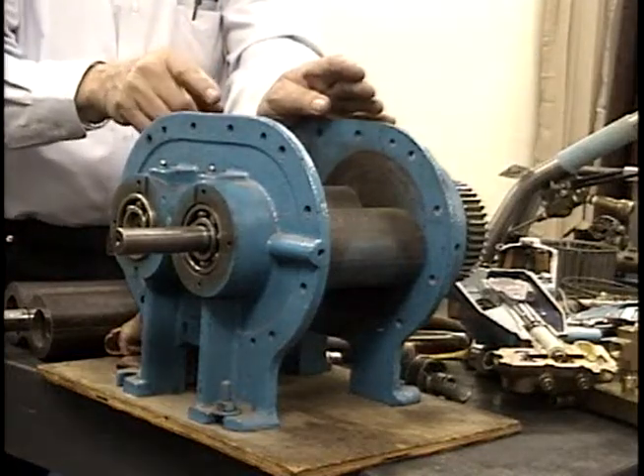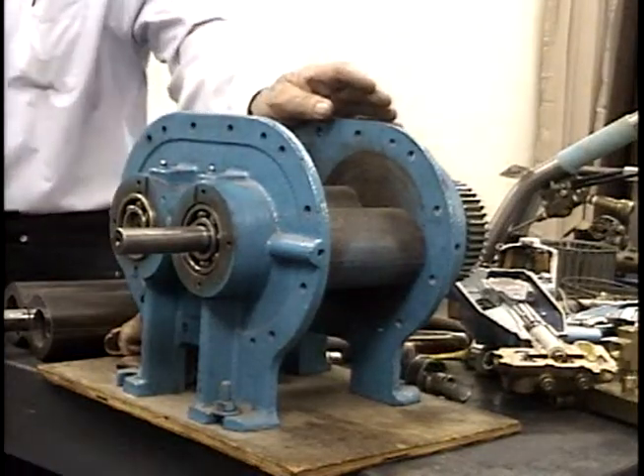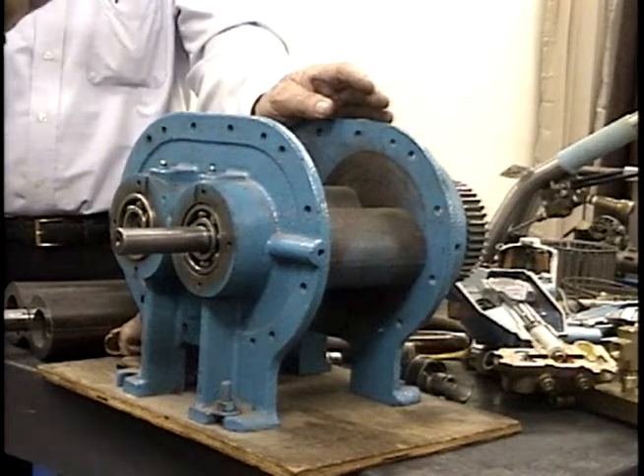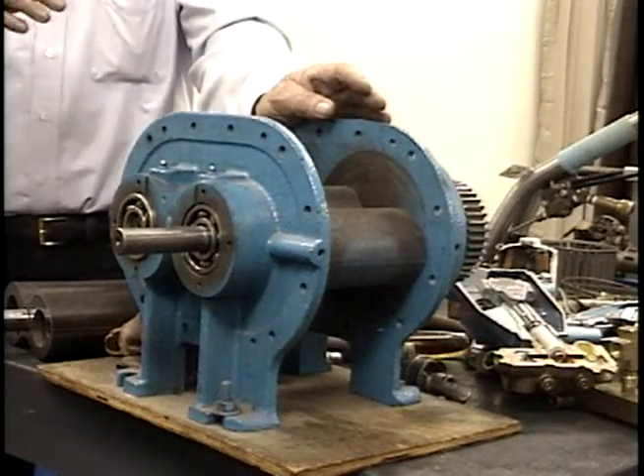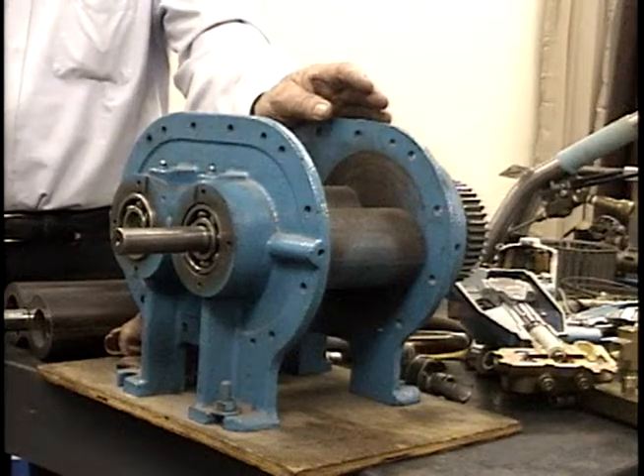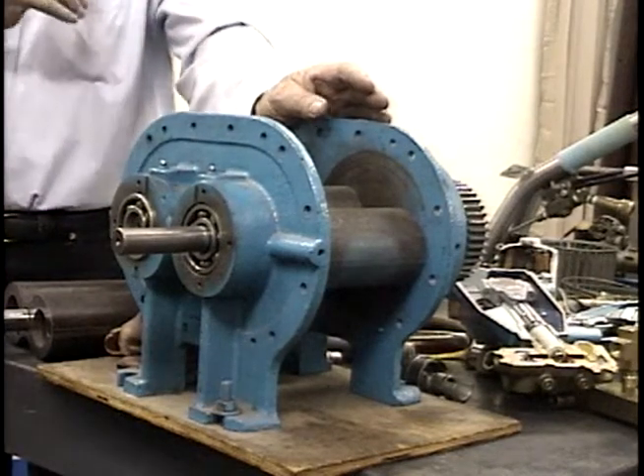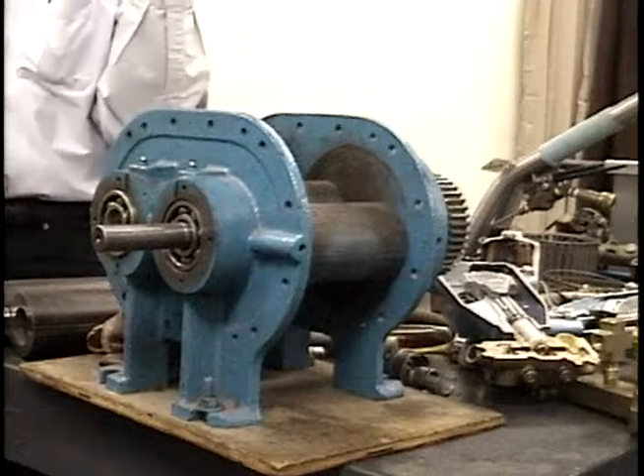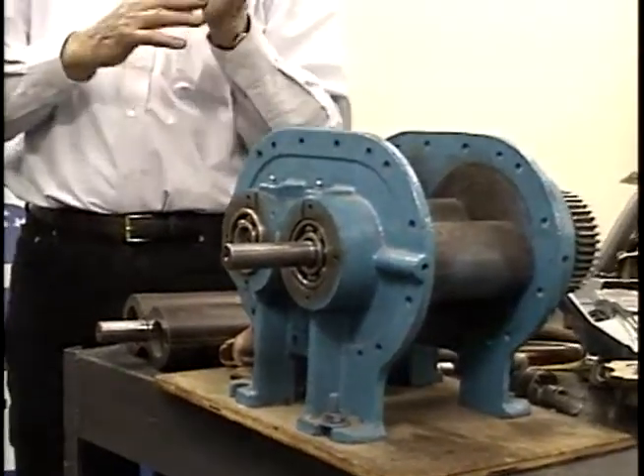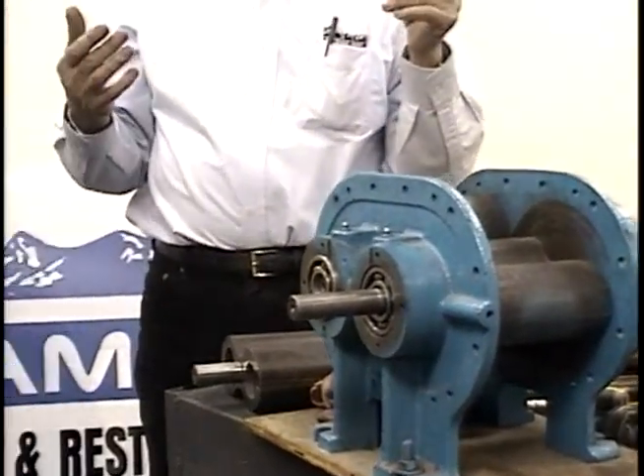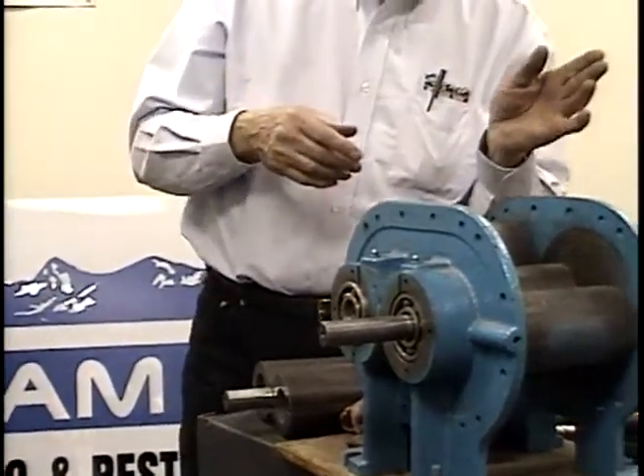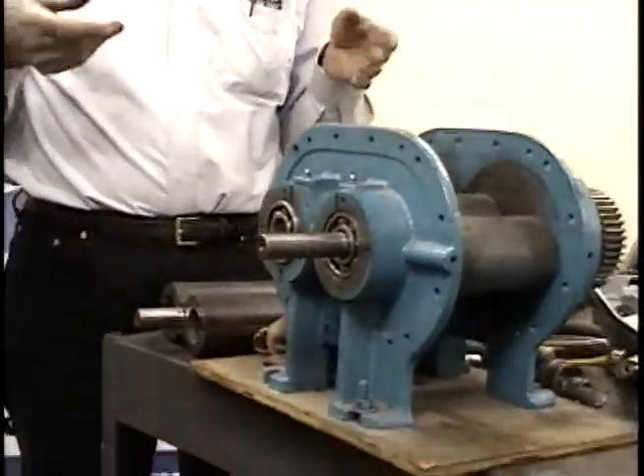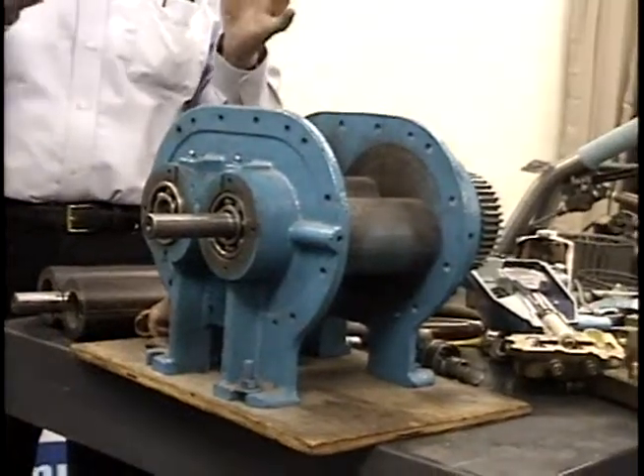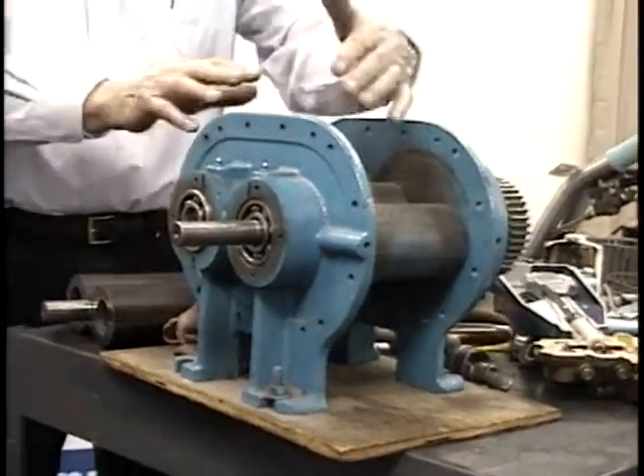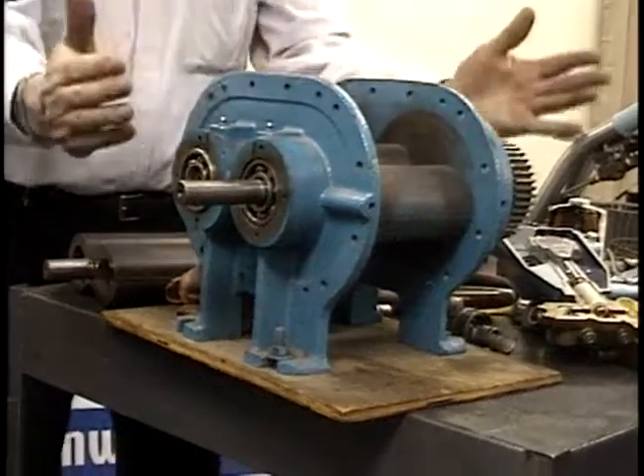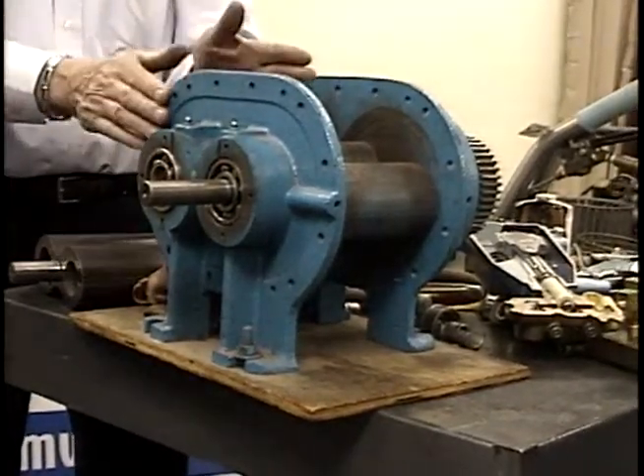So we want to find out how to wash these out. We recommend, if you have a blower, at the end of the day shooting a little clean water through it, letting it air dry for a minute or two, then shooting some WD-40 through it. We put a special place on your machine, a blower oiler/washer-outer port, so you can do this procedure without doing anything drastic. If we keep the inside clean and the bearings and gears clean, we ought to keep this blower running for many, many years.